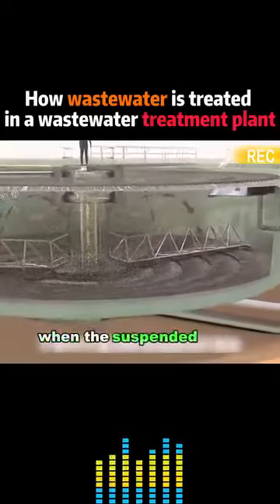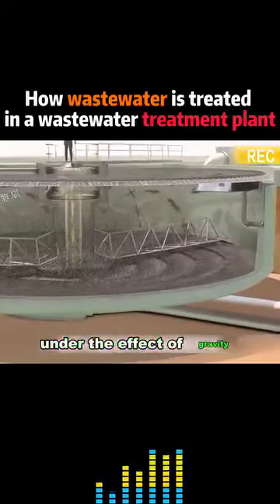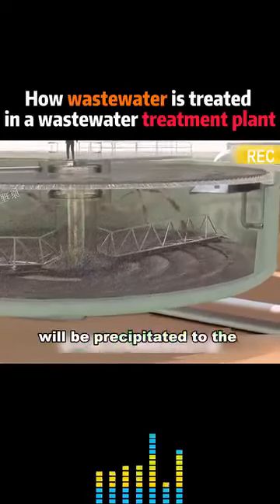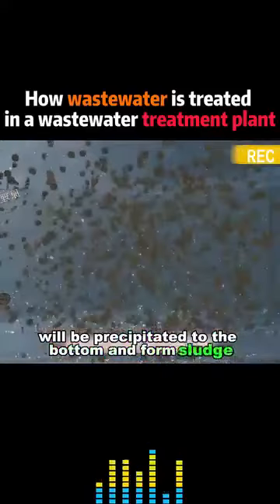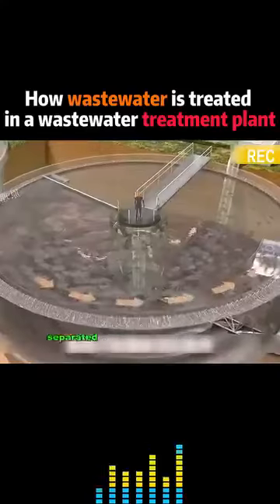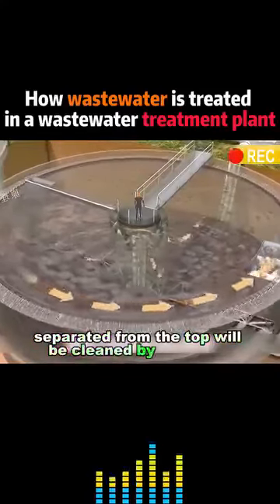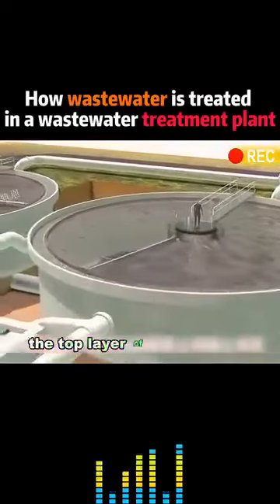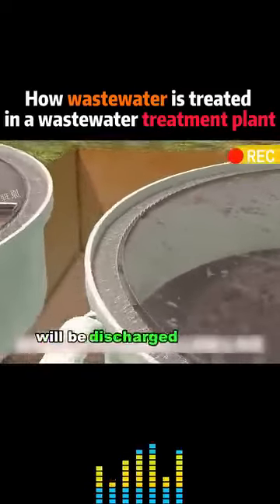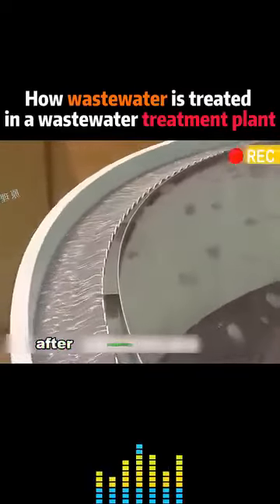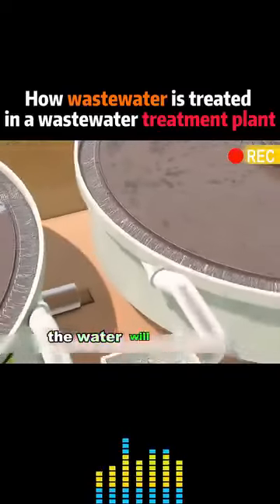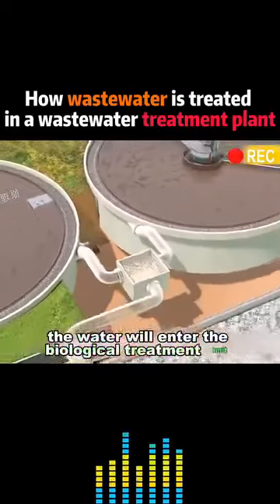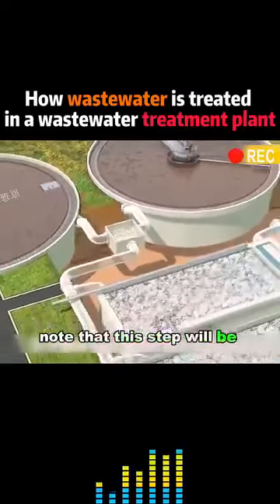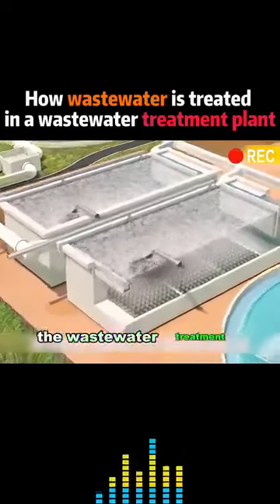The suspended solid debris, under the effect of gravity, will be precipitated to the bottom and form sludge. The oil and grease separated at the top will be cleaned by a scraper. The top layer of supernatant will be discharged through the weir. After preliminary treatment, the water will enter the biological treatment unit. Note that this step is the key part of the wastewater treatment.